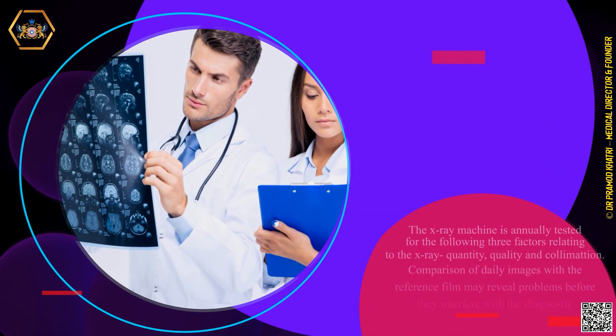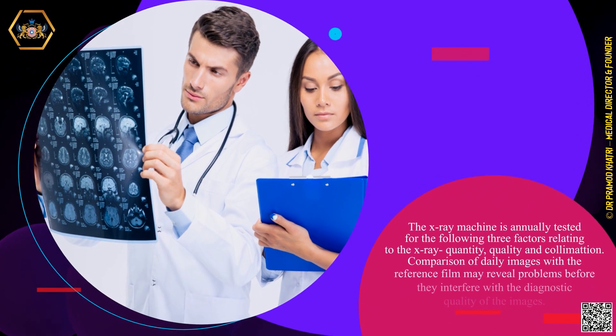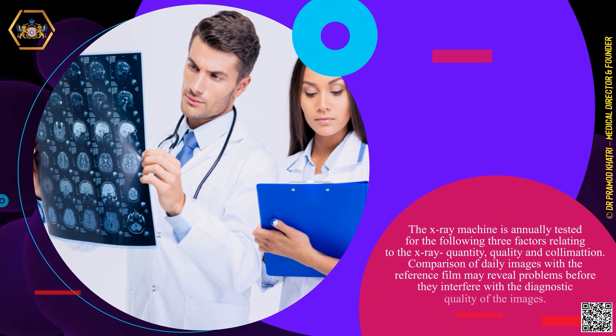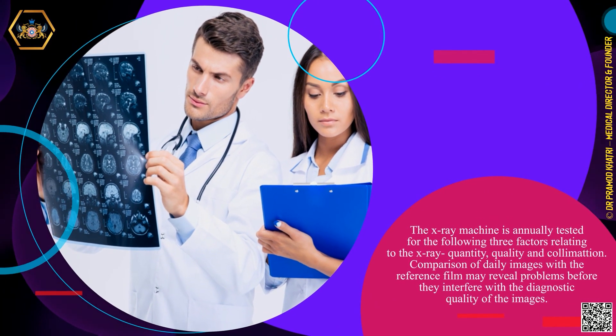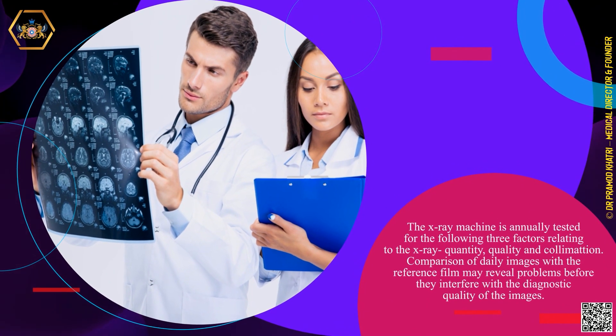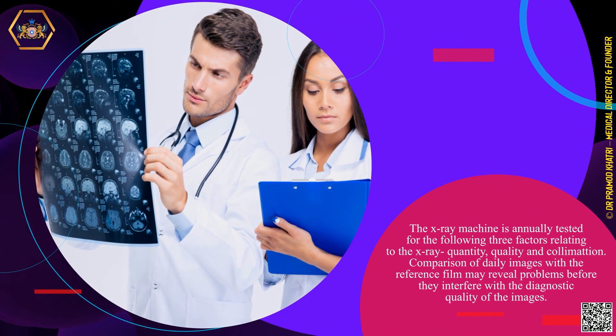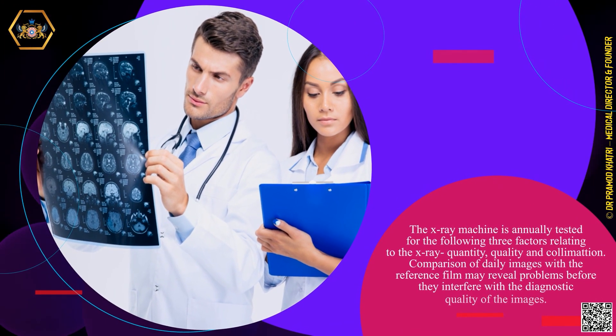The X-ray machine is annually tested for the following three factors relating to X-ray quantity, quality, and collimation. Comparison of daily images with the reference film may reveal problems before they interfere with the diagnostic quality of the images.